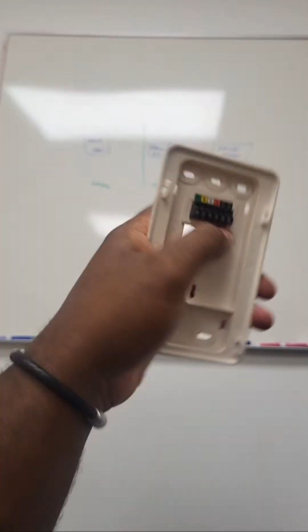But basically, guys, I first started with checking for power, and I actually did have power between C and D. And next, I looked at the wires. I made sure that my wire configuration was the same from one end to the other. Next, guys, after I did that, based on me having power and the wiring configuration being correct between my thermostat and my furnace, I knew that this thermostat was shot. So what I ended up doing was, this is an older style Infinity setup, I ended up putting in the newer Carrier Infinity thermostat, and I had to get that from Carrier.